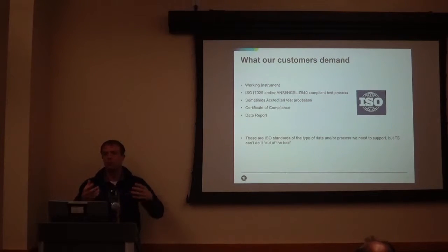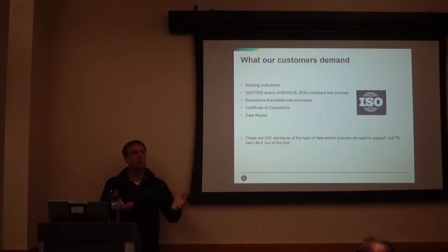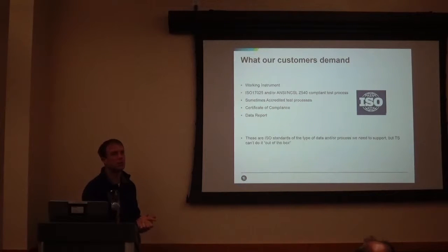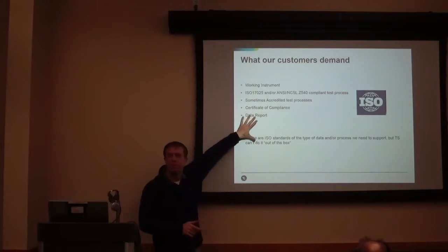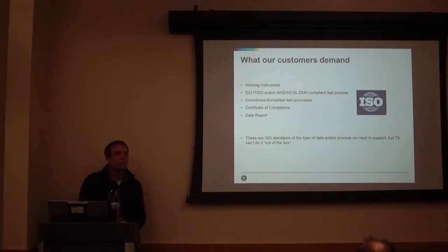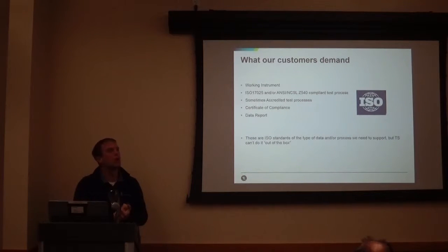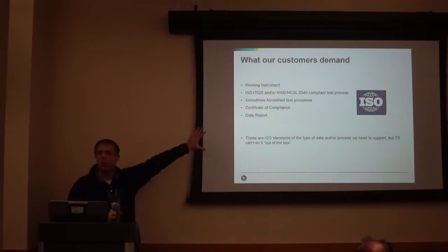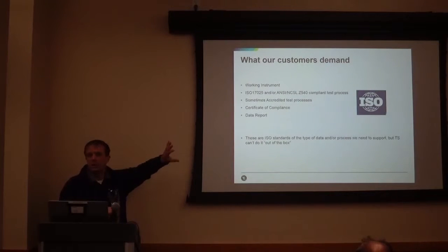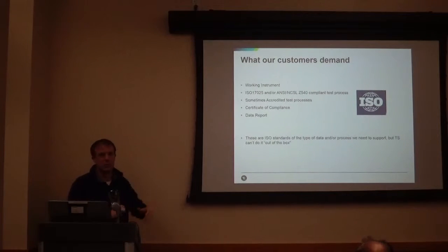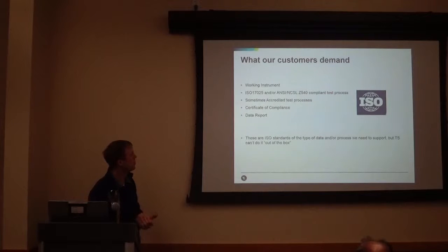And we're shipping off a certificate of compliance or traceable calibration to you that provides all those measurements and tries to convince you that we're doing it right with a data report. So that's all really different than just getting a green screen at the end that says motherboard passed. And that type of stuff TestStand doesn't do well. All the features aren't quite there out of the box. NI's been getting better, so some of this has improved, but not all the way there with the newer versions.